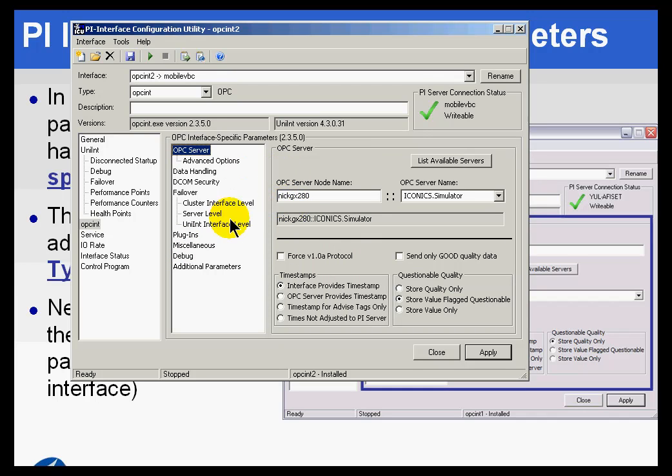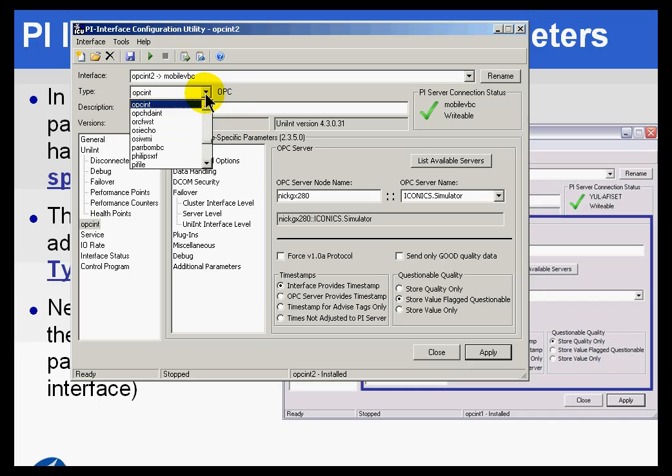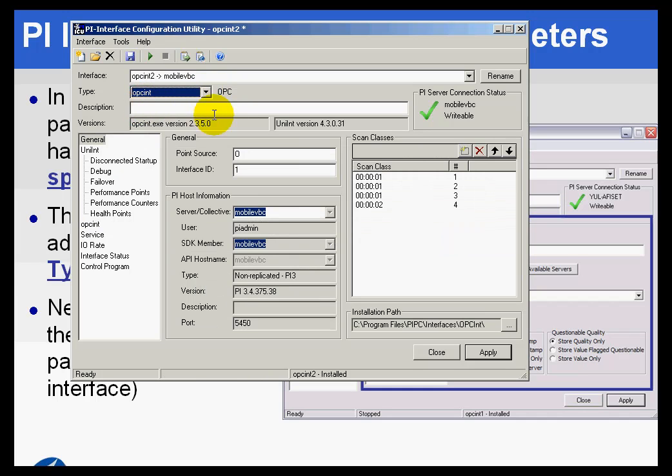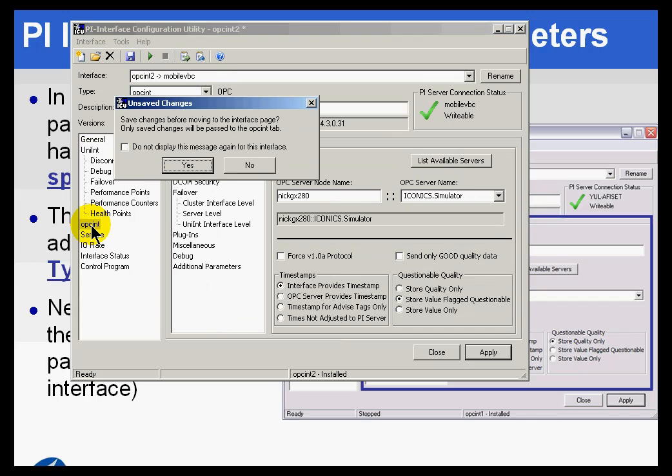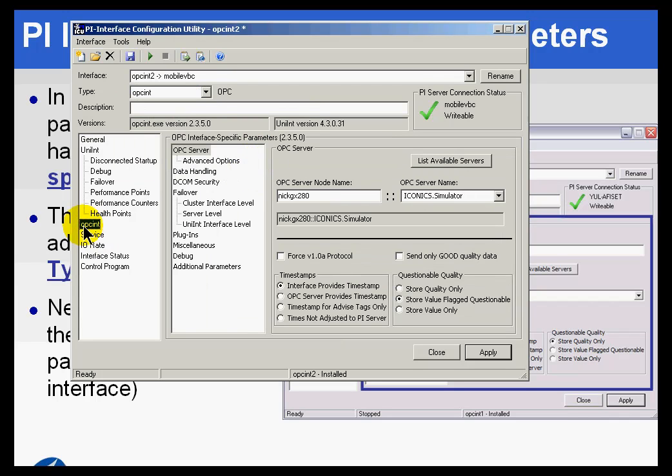And by the way, one minor point: if you do import an OPC interface, or any interface, and its type has been set properly, and for some reason when you click on the interface-specific tab, if you don't see anything, if it's just a blank screen, that means you probably don't have what's called the ICU control that goes with that interface.